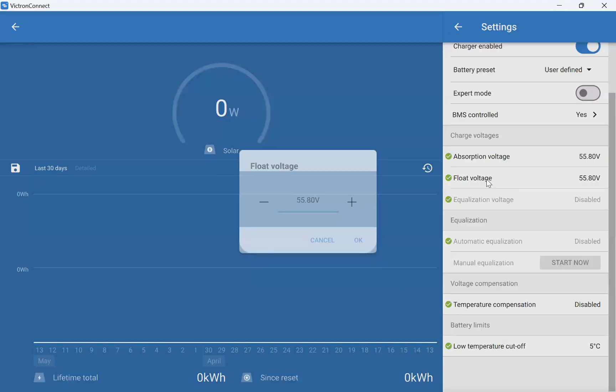You can see equalization is disabled. Now notice these ticks over here — watch this, look at that green tick. As I change this, I'll set it to 55 as an example. It will circle around and then tick, and that tick means the setting has been accepted by the charge controller in real time.